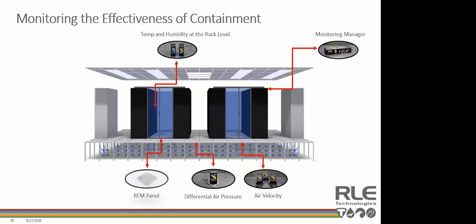So the RLE Wing Manager receives and aggregates signals from the wing sensors. This data is displayed on a web interface accessible from any browser or mobile device. Designed to keep the most relevant information close at hand, the web interface provides direct alarm notification, which allows users to quickly and effectively locate areas of concern. The Wing Manager will also send email alarm notifications and provide trending information to help pinpoint trouble spots in any monitored area. With wing sensors, you can measure temperature, humidity, differential air pressure, and air velocity.